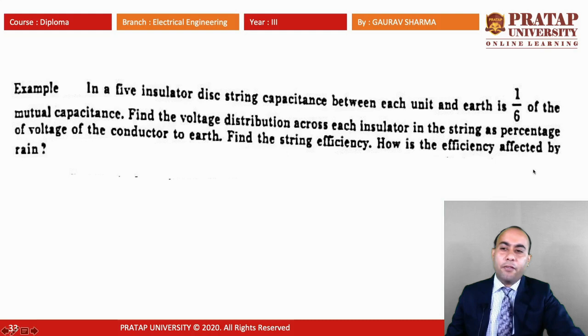Now, we draw the diagram for the 5 disc insulator. The equivalent circuit of the 5 disc insulator is shown in the figure. The ratio of the capacitance to the mutual capacitance, K, which is equal to C1 by C, is given as 1/6. Now, let the voltage of the conductor to earth be V volts. Now, we have V2 is equal to V1 into 1 plus K. We put the value of K and we have 7/6 V1, or 1.1667 V1. Now, from this formula, we also calculate V3 and V4.